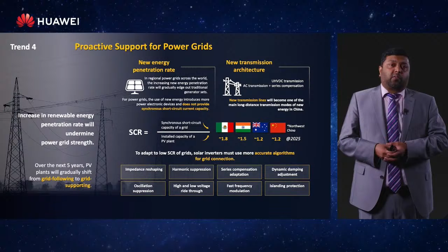The inverters are not just converting DC to AC, but also providing grid support services. In the future they can work not just as a current source but also as a voltage source, forming the grid—what we call grid forming converters or grid forming inverters. The short circuit ratio trend is going down, below 2.0, and in the next 5 years we'll see a lot more proactiveness, grid friendliness, and control algorithms going inside the inverter.